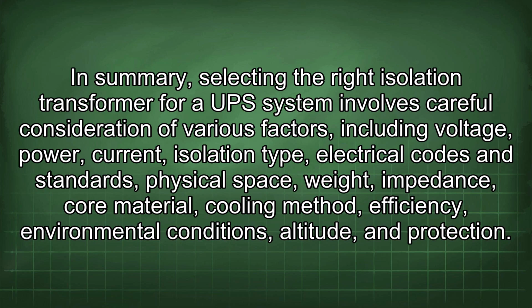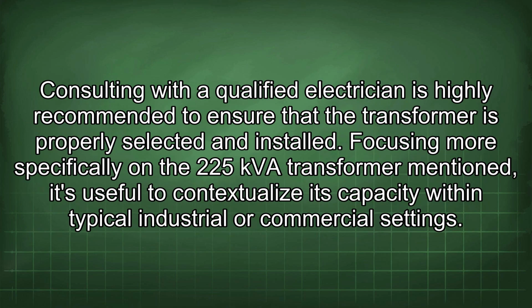In summary, selecting the right isolation transformer for a UPS system involves careful consideration of various factors, including voltage, power, current, isolation type, electrical codes and standards, physical space, weight, impedance, core material, cooling method, efficiency, environmental conditions, altitude, and protection. Consulting with a qualified electrician is highly recommended to ensure that the transformer is properly selected and installed.